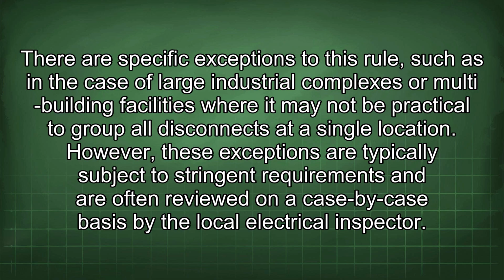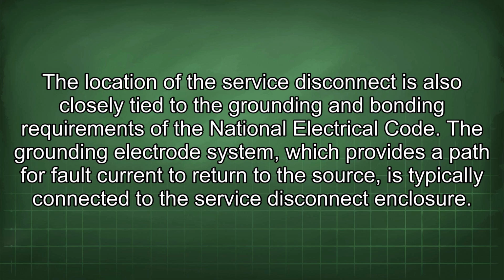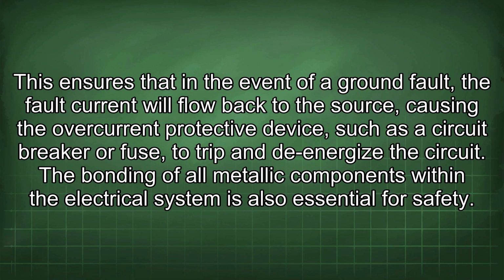The location of the service disconnect is also closely tied to the grounding and bonding requirements of the National Electrical Code. The grounding electrode system, which provides a path for fault current to return to the source, is typically connected to the service disconnect enclosure. This ensures that in the event of a ground fault, the fault current will flow back to the source, causing the overcurrent protective device, such as a circuit breaker or fuse, to trip and de-energize the circuit.